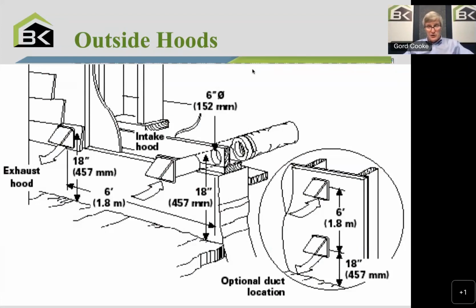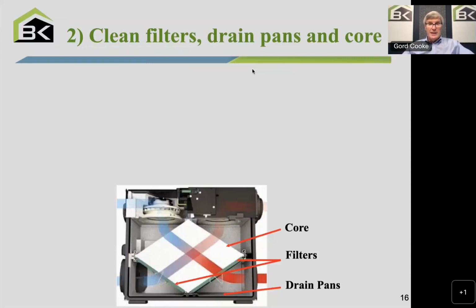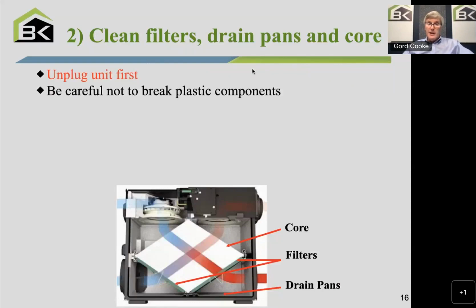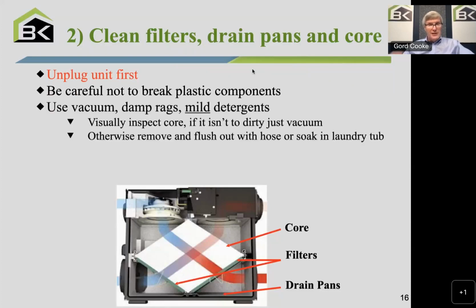You don't want them too low to the ground because they tend to then pick up more dust and dirt and so on. So that's the outside hoods. And then next, I'll just put these up. We're going to clean the filters, the drain pans, and the core. So first, we're going to unplug the unit. Just to remind you, it's probably already unplugged, should be, but I just want to reiterate that. And be a little careful, as I mentioned, not to break plastic components. And here you're using typically a vacuum cleaner, some damp rags, mild detergents, nothing fancy here.